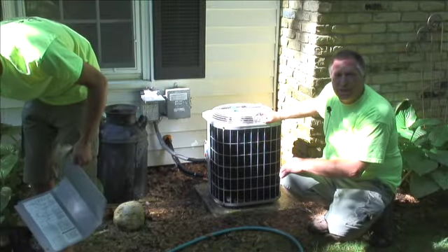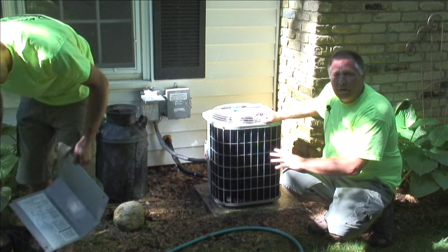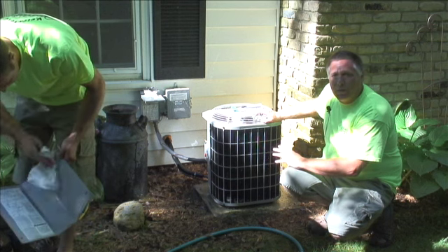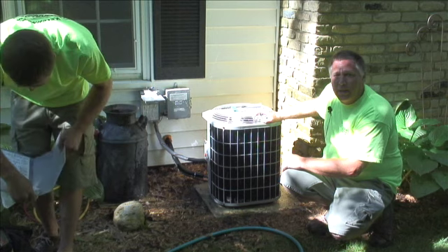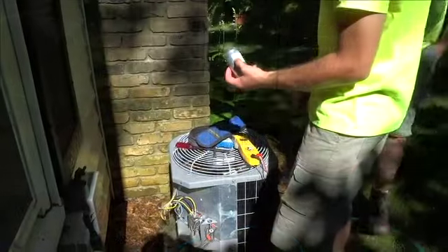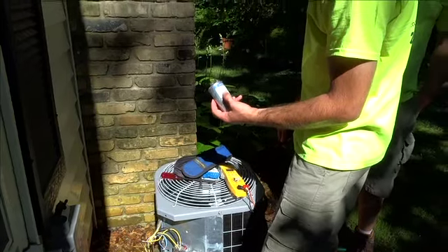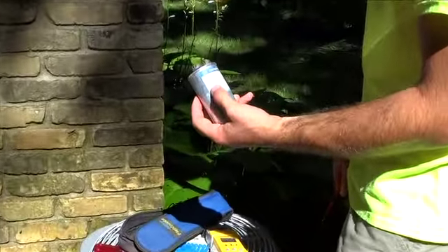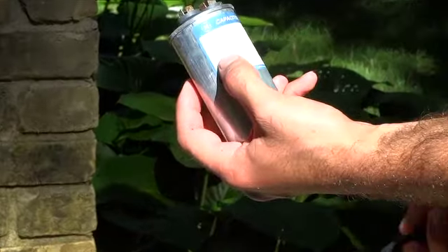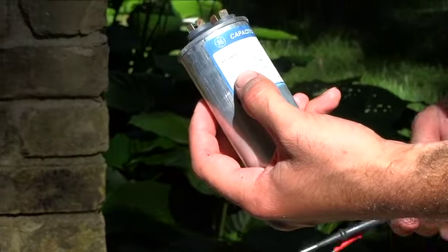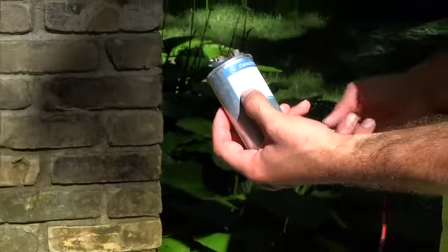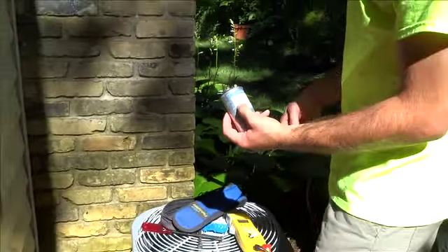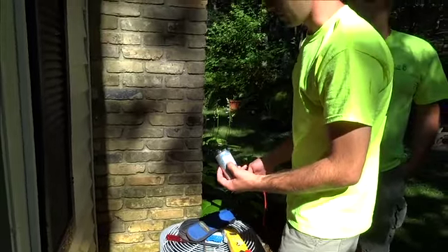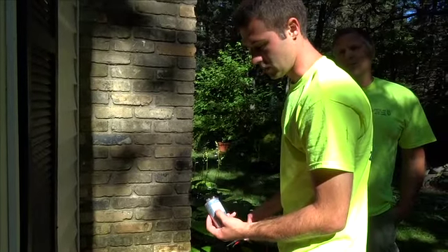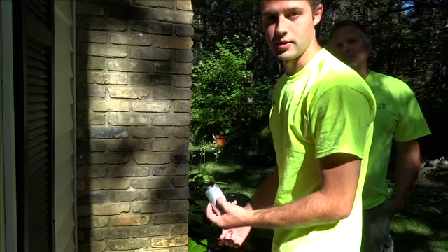Now we'll check the capacitor and the contactor and the wiring for proper electrical voltage and to make sure no rodents have been in there over the winter time to chew off any of the wiring. Each capacitor has a rating on it and also a plus or minus value of what it can be. As long as it's within a certain range, the capacitor is still proper and working okay. Once they get out of that range, they make the electrical motors, both the fan and compressor motor, work harder, therefore shortening the life of them.